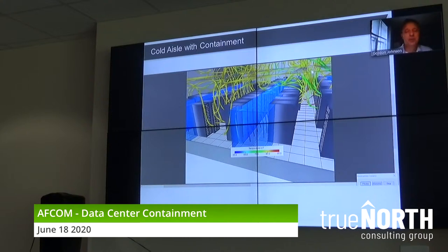At this point, I can now do some cooling optimization in this data set. I can raise temperatures. I might be able to lower fan speeds, but I definitely can save some money. One last thing before I continue, one common misconception with cold aisle containment, which is what I'm showing here, is people say, if I contain the cold aisles, the rest of my data center is one big hot aisle. That's true. But people say, I don't want to walk into a hot aisle.